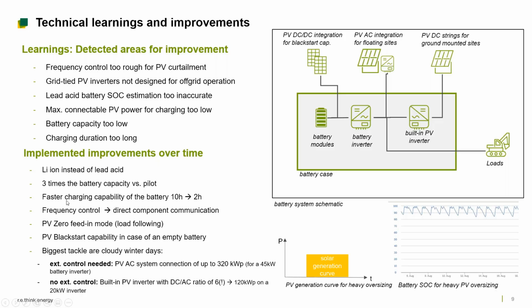We enabled fast charging capability to reduce the charging time from like 10 hours down to 2 hours. We moved from frequency control to direct component communication. We implemented a PV 0 feed-in mode for these grid-tied inverters to have them still on the grid, but not producing any energy in case of a full battery and no more load.